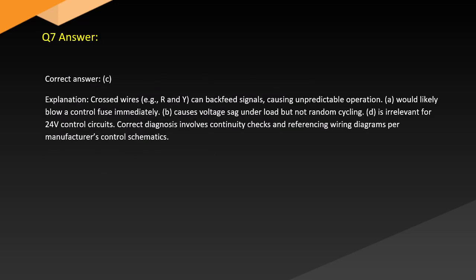Answer. Correct answer: C. Explanation. Crossed wires, such as A, G, R and Y, can backfeed signals, causing unpredictable operation. A would likely blow a control fuse immediately. B causes voltage sag under load but not random cycling. D is irrelevant for 24-volt control circuits. Correct diagnosis involves continuity checks and referencing wiring diagrams per manufacturer's control schematics.